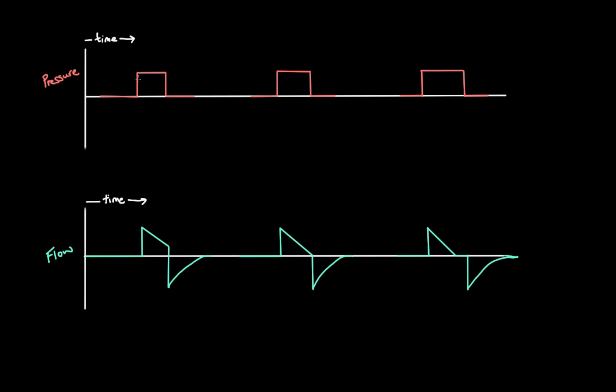I haven't used any units because they're not really relevant to understanding the concept. You can see how this would be a breath — the inspiration, a pressure-controlled breath. We elevate the pressure to a certain point and hold it there for a certain amount of time. We set the inspiratory time on the ventilator. From here to here is our pressure control level.